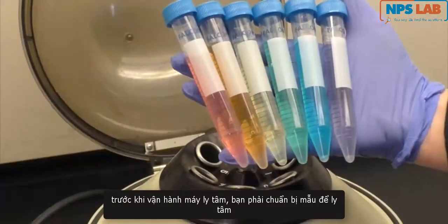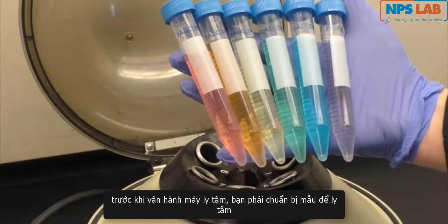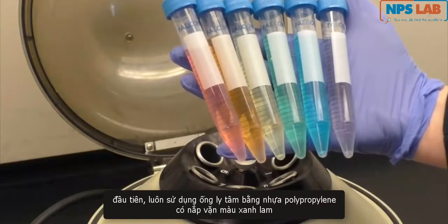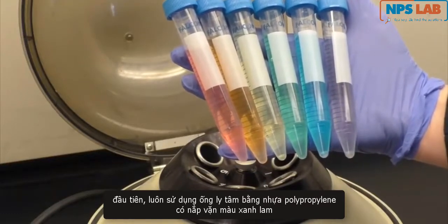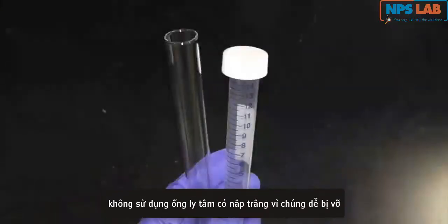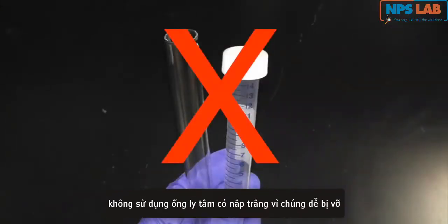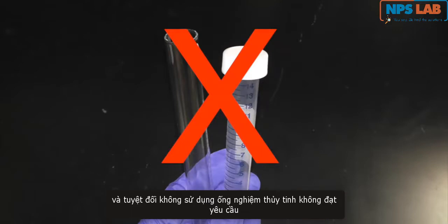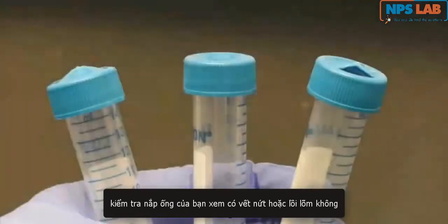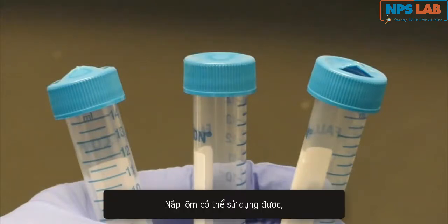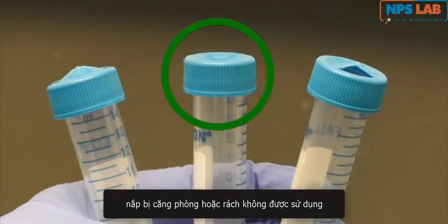Before operating the centrifuge, you must prepare your sample for centrifugation. First, always use a polypropylene centrifuge tube with a blue screw cap. Do not use a centrifuge tube with a white cap as they tend to break easily, and never use glass test tubes. Check the cap of your tube for cracks or protrusions. Caps that are concave are usable, while caps that are distended or splitting should not be used.